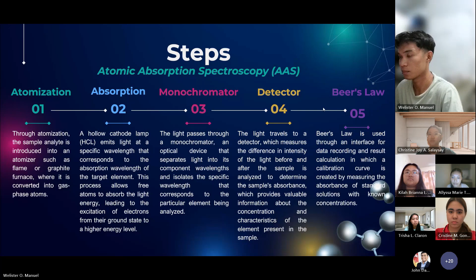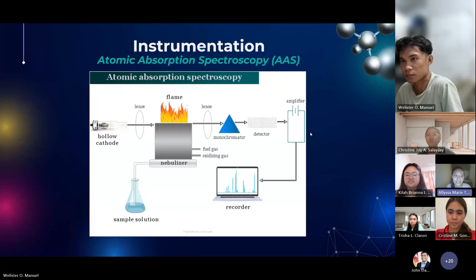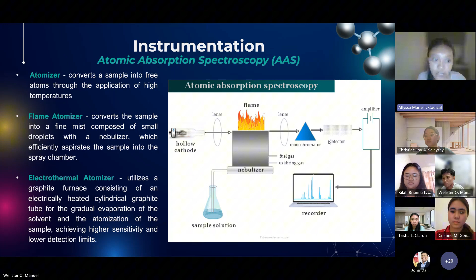First, we have the atomizer, which converts the sample into individual atoms by introducing it into a flame or graphite furnace where the sample is heated until its atoms turn into a gaseous state. We have 2 types of atomizer, which are the flame atomizer that uses a flame and a nebulizer to turn the sample into fine mist-like droplets. Second, we have electrothermal atomizer, which uses an electrically heated tube, such as graphite furnace, for gradual heating.